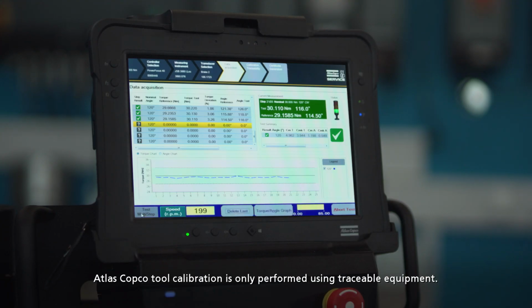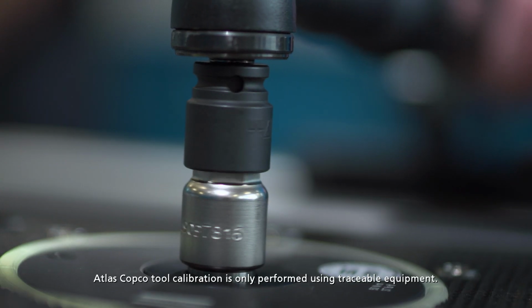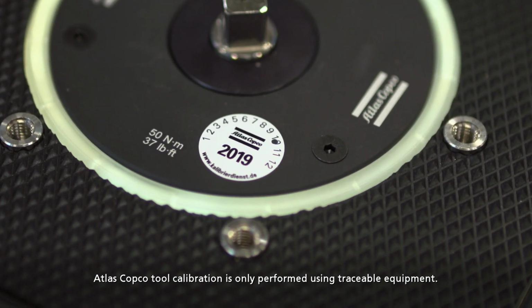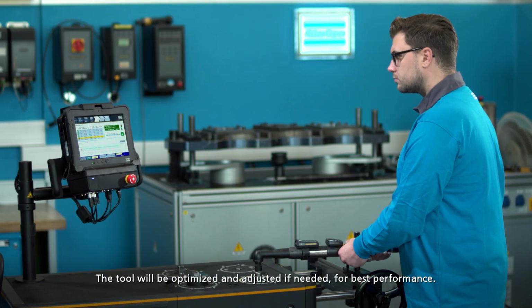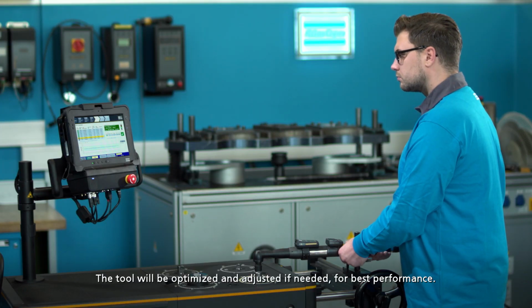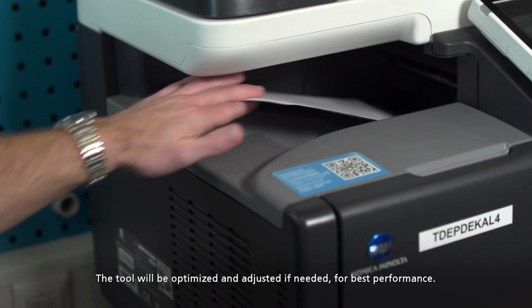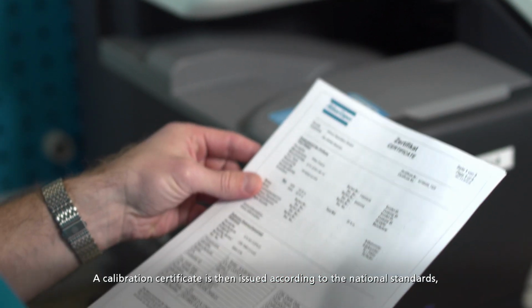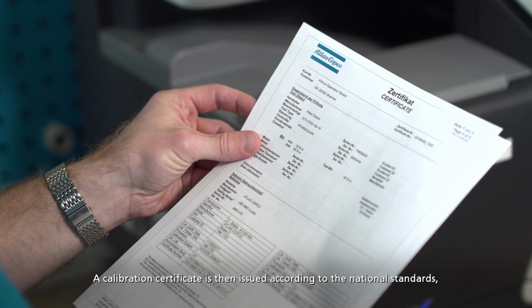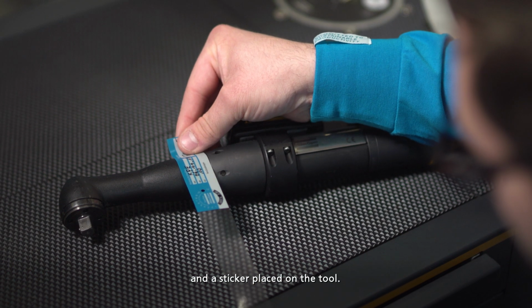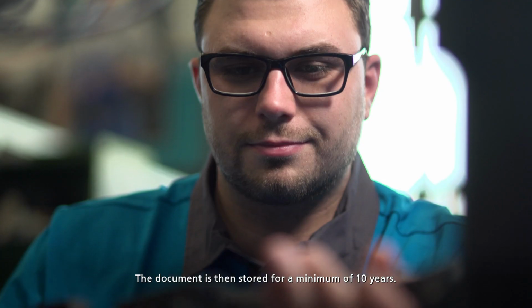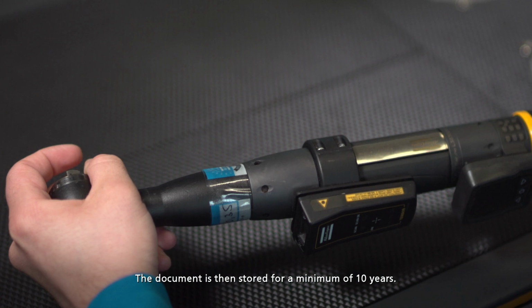Atlas Copco tool calibration is only performed using traceable equipment. The tool will be optimized and adjusted if needed for best performance. A calibration certificate is then issued according to the national standards and a sticker placed on the tool. The document is then stored for a minimum of 10 years.